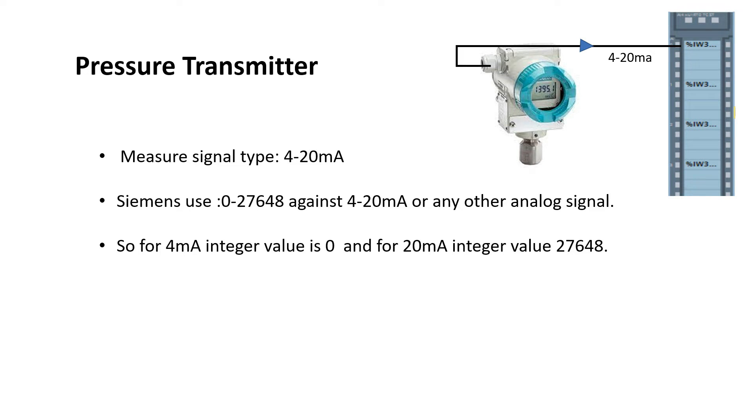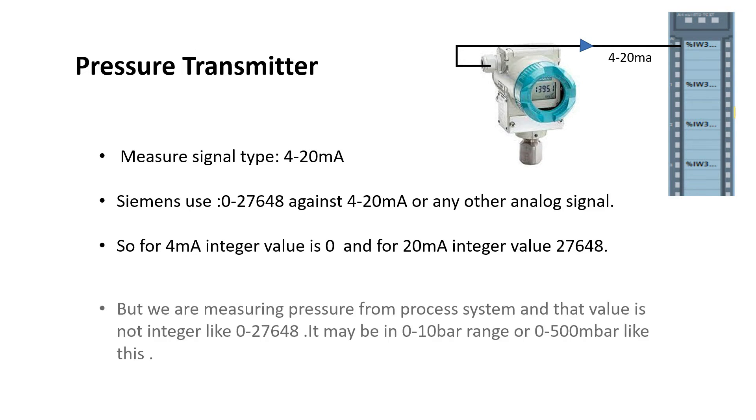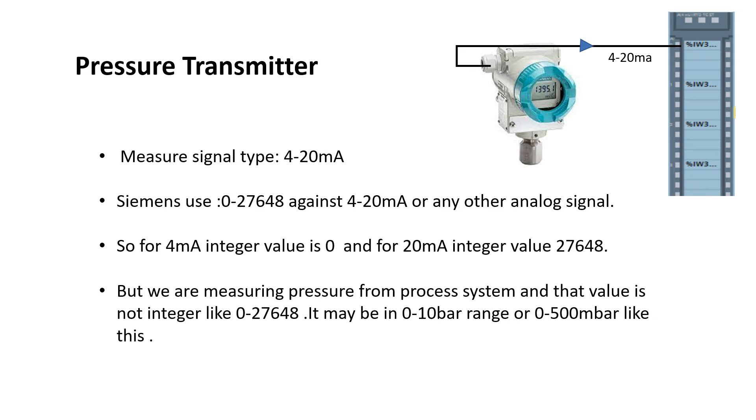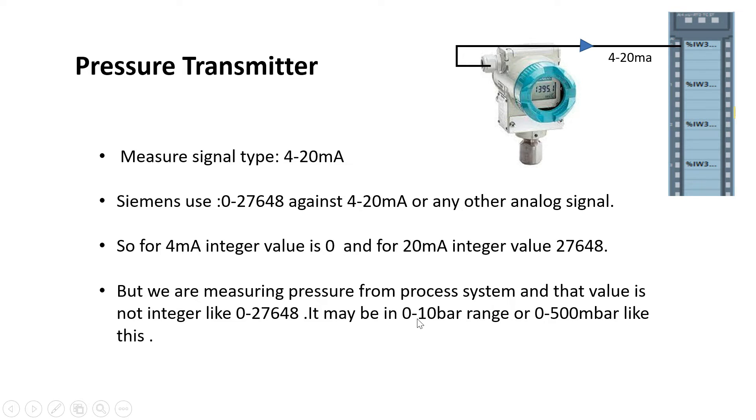So for 4 milliamp it is 0, and for 20 milliamp it is 27648. This range. But we are measuring the pressure from the process system, and that value is not an integer like this. It may be 0 to 10 bar range or 0 to 50 millibar or 500 millibar like this.